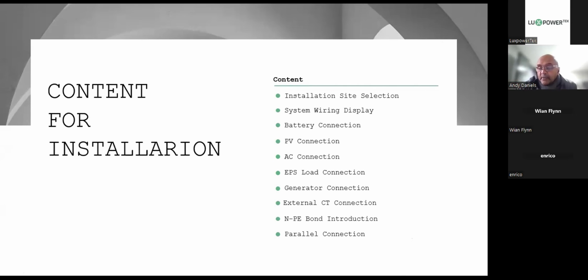There is an enable and disable button for neutral potential earth bonding, but that does not apply to the 5 kilowatt machines that we've got in stock that we are currently selling. We've got to wait for those to sell out before we bring in the ones with the bonding relay. But the new 6s, we brought in a limited amount of, I think there were 200 machines brought into the country. And those are already all sold and installed. Those machines do come with the bonding relay, so you can make use of that.